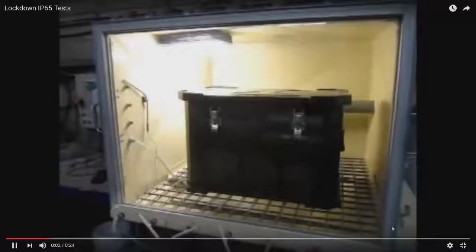So, left top, can you see there IP65 tests are given. The test house does not guarantee that each and every unit conforms to this, because a lot depends on how you install it and what happens to it the first time you attempt any repair. However, the test house gives a certificate saying under what conditions they ran it, with the understanding that we conducted it on the samples given to us.